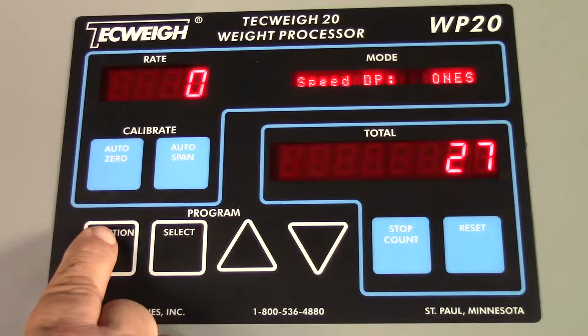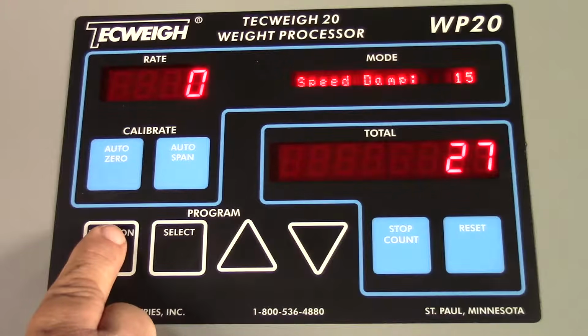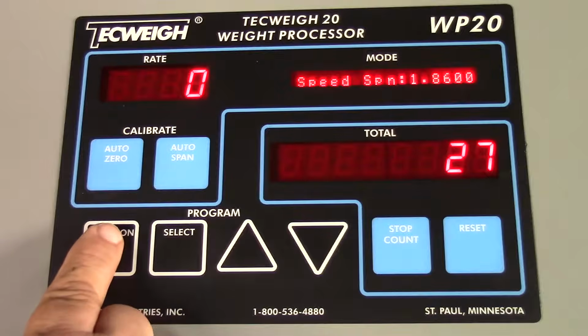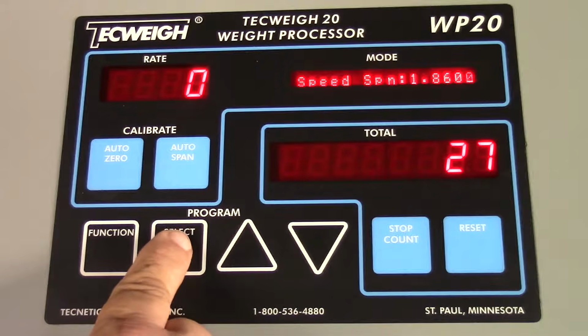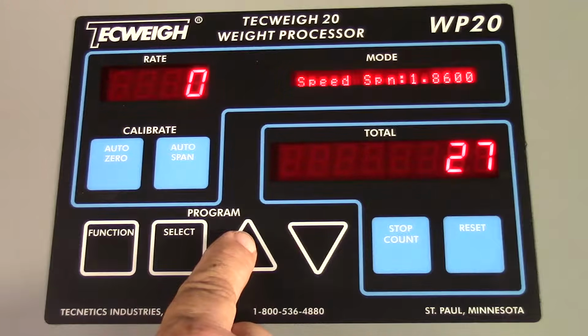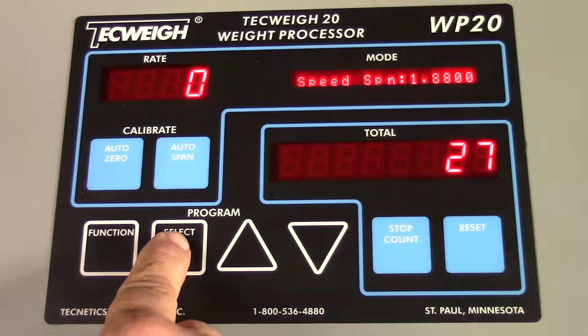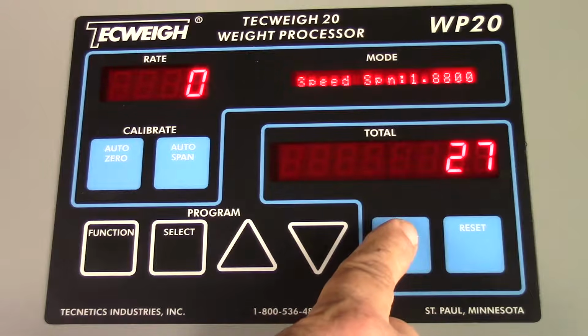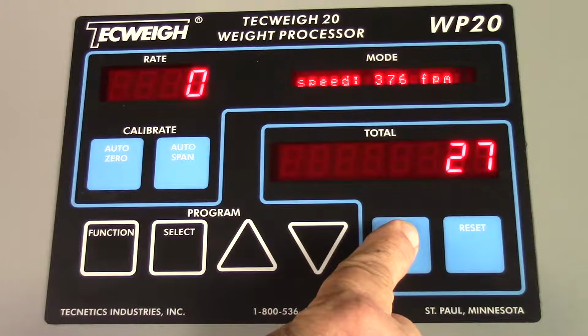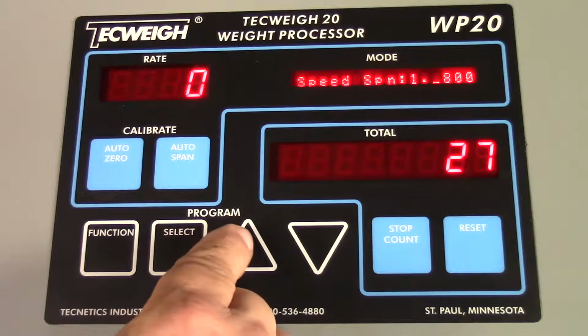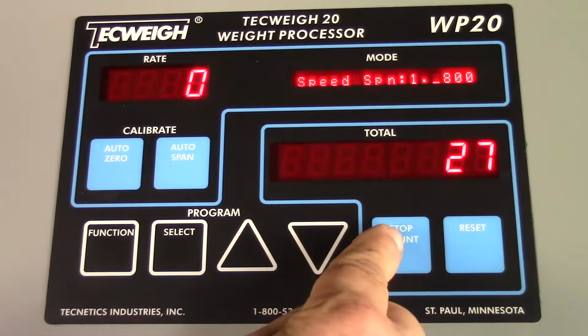Speed decimal places, that's just like the rate decimal place, meaning we could go in and adjust that. Speed damping, if we wanted to change that, add some damping on the speed value, but generally that's not required. The speed constant, this is going to be pre-programmed for the particular type of speed sensor, but if you measure the belt speed as it actually is, you can go in and adjust that up and down. If you hold down the stop count, it'll show you the belt speed, so you could adjust that value up and down till you arrive at the speed you measured, maybe with like a handheld tachometer.